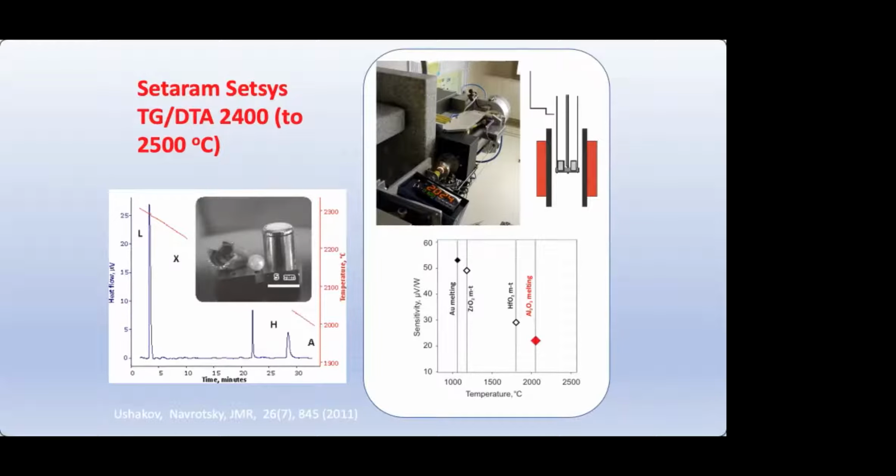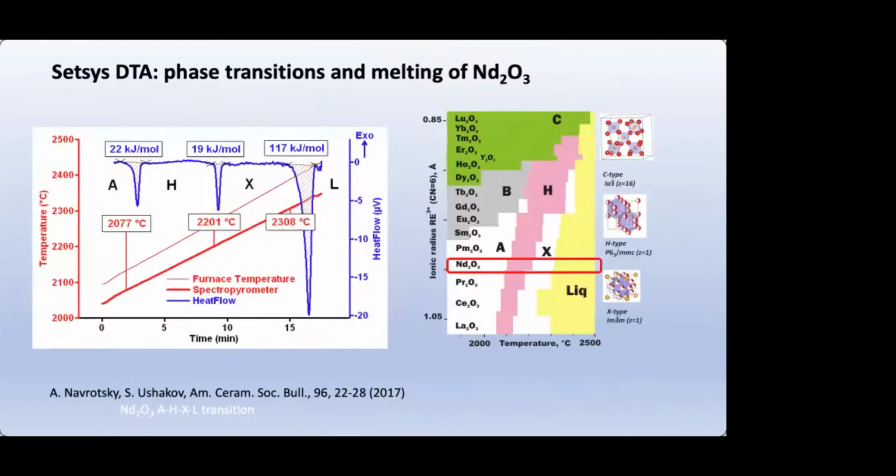But we soon realized that we cannot extrapolate those values very well to even higher temperature, and we sought other materials, perhaps yttrium oxide, that melt at higher temperatures as calibrants, and we saw inconsistencies in published data, an interesting realm perhaps for CALPHAD, that made us think we needed to remeasure some of these materials at high temperature, and led to the ability to quantify these results once we have a calibration.